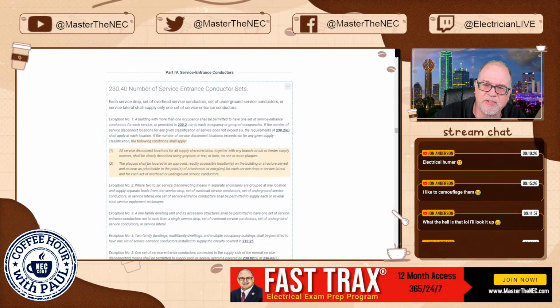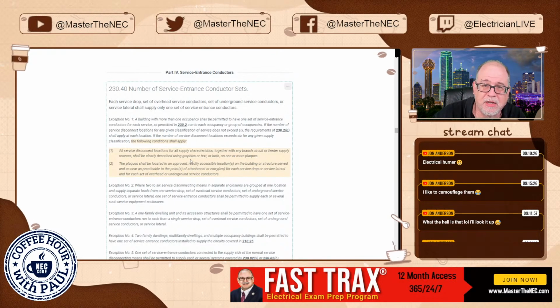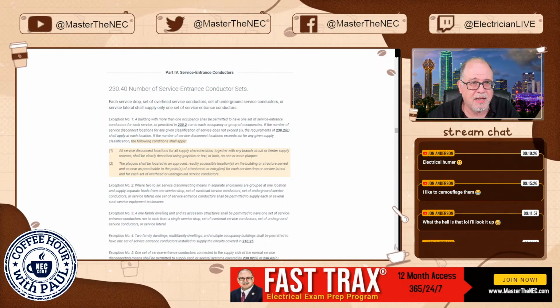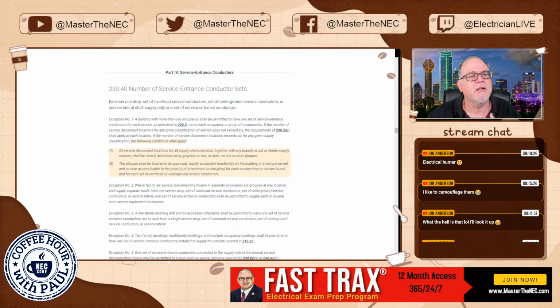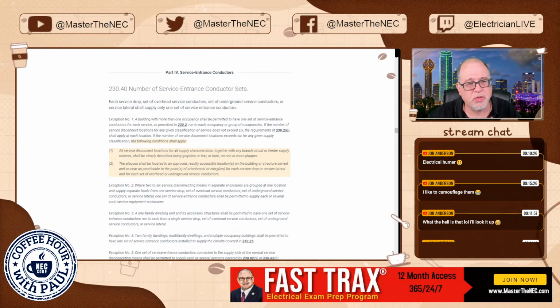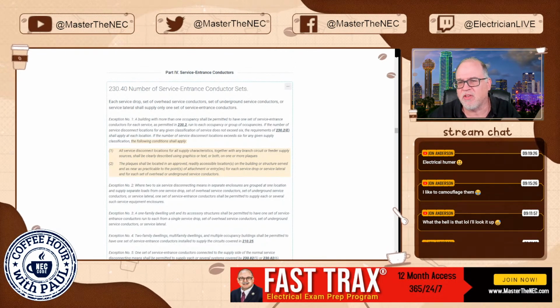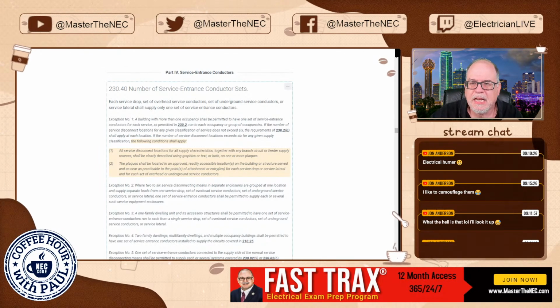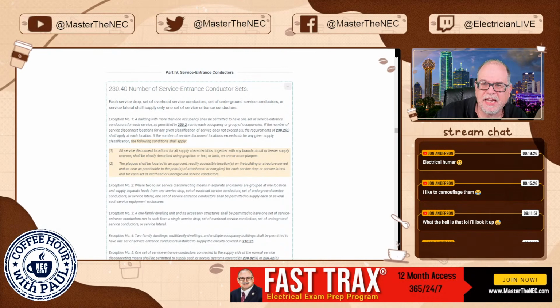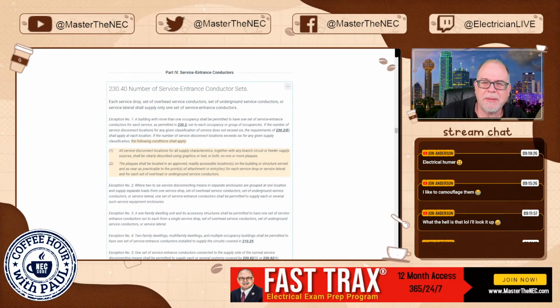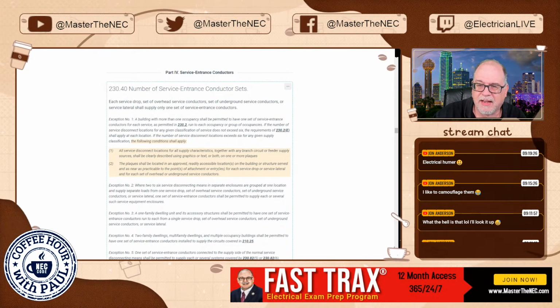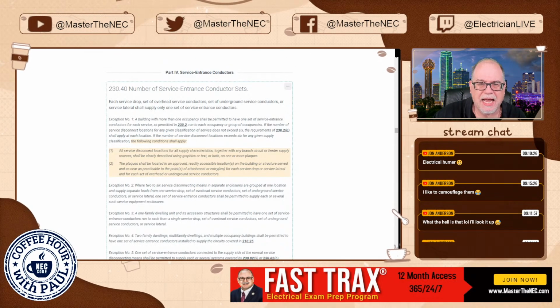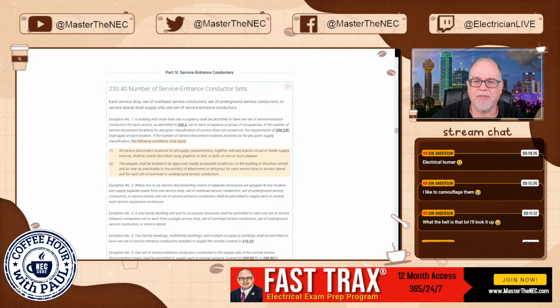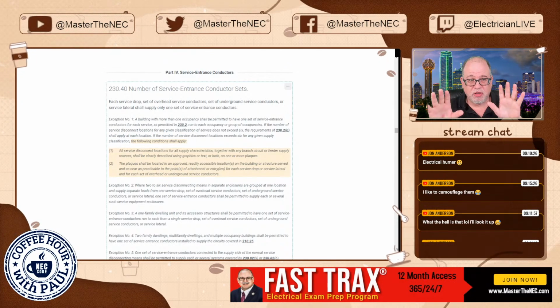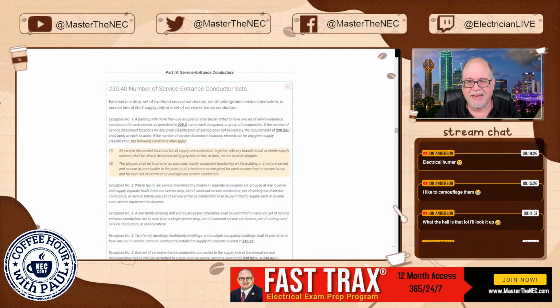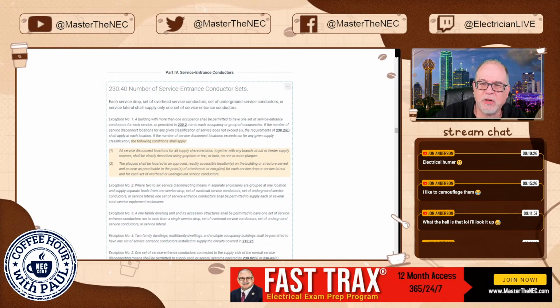It says all service disconnects located for all supply characteristics, and again, those characteristics are found at the beginning of the code. At the beginning of 230, that would be 230.2, all of those type of things. Different services and the number of services and the characteristics that are involved. If you have that, together with any branch circuit or feeder supplying sources, shall be clearly described using a graphic or text or both on one or more plaques. Okay, so you have to have all of the locations graphically or in text format telling you where they are. Okay, and again, this is where you exceed 6.